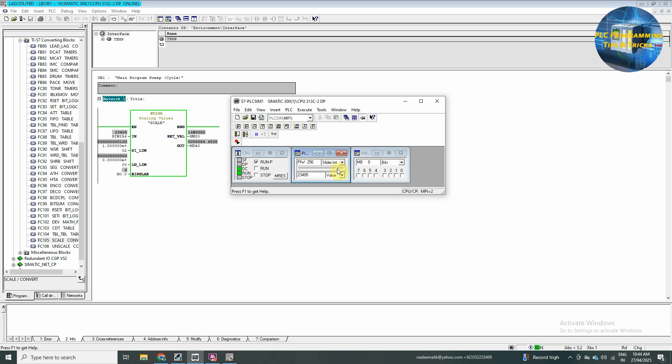So, this block is basically converting the input word into 0 to 100% and scaling it to an MD output. For example, if we connect the temperature transmitter at PIW 256 and it's scaling is 0 to 150 degrees, what that will do, it will convert with my input, 4 to 20 milliamp signal into 0 to 150 degrees.